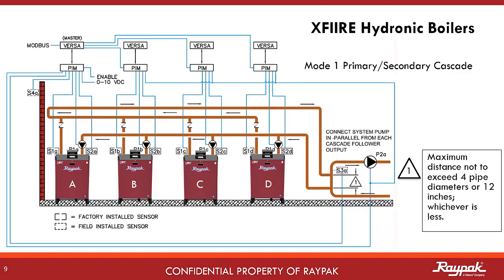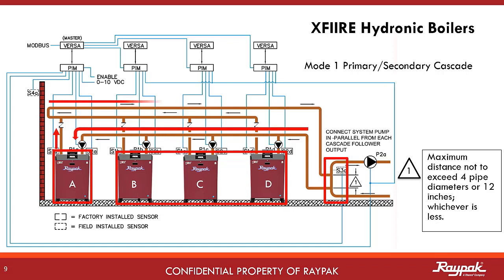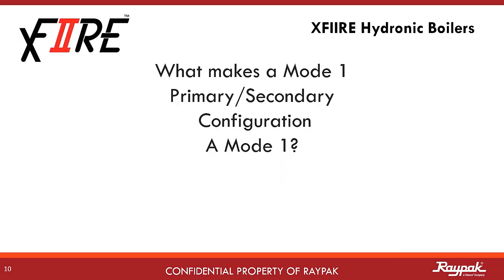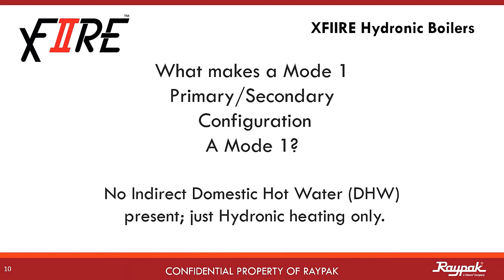Mode 1 can also be run in a cascade system. Here, boiler A on the left is the master boiler and boilers B, C, and D are the followers. There is one decoupler for the system and it supports the entire cascade. An important part of plumbing boilers in cascade is to use reverse-return logic: the first boiler out to the loop is the last boiler to receive water back from the loop. What makes a Mode 1 primary-secondary a Mode 1? It is not what is there, but what is not there — there is no indirect domestic hot water system present. It is just a straight-up hydronic heater.